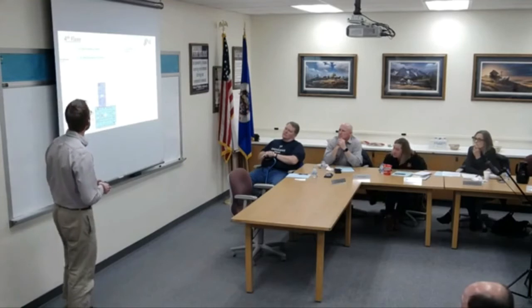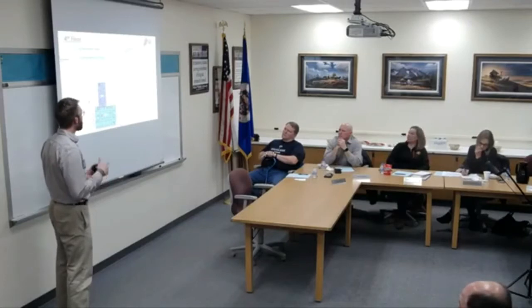Going back to what Jeff touched on, the indoor air quality issues with high CO2 levels affect the fourth floor as well as the third floor. That would trigger the need to recommission the units serving those spaces—bringing in service technicians to rebalance the outside air flows and make sure the air flow in CFM is at the right level, which should help address the indoor air quality issues in those spaces.